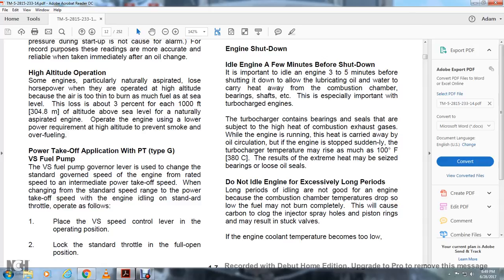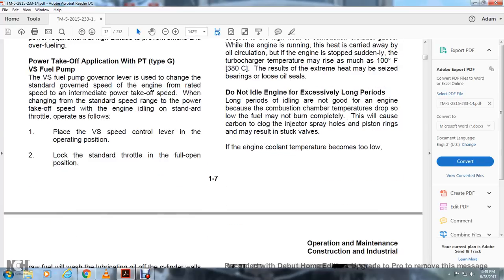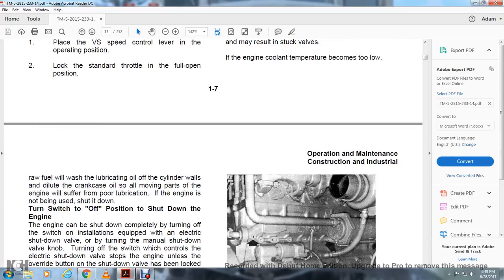Do not idle the engine for an excessively long period. Long periods of idling are not good for the engine because the combustion chamber temperature drops so low that the fuel may not burn completely. This will cause carbon to clog the injector spray holes and piston rings, and may result in stuck valves, and the engine coolant temperature becomes too low. Raw fuel will wash the lubricating oil from the cylinder wall and dilute the crankcase oil, so all the moving parts of the engine will suffer poor lubrication. If the engine is not being used, shut it down.